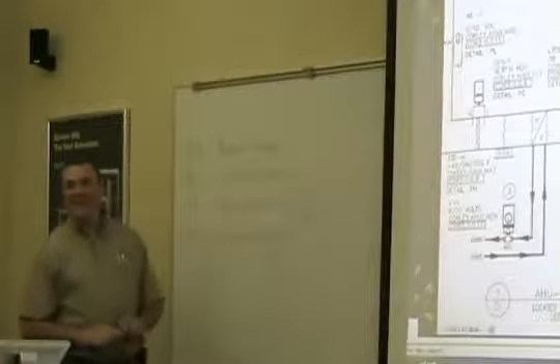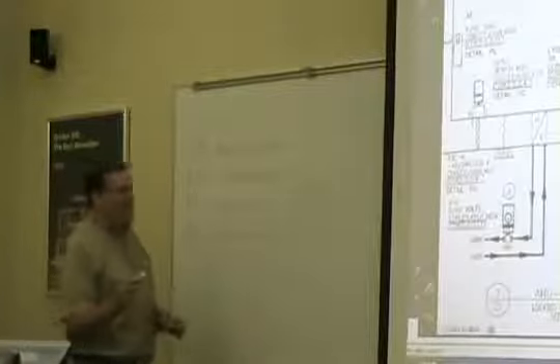Increase in temperature because of the fan. Right. Okay. You can pick up 2-3 degrees of heat across the fan. And some customers, some engineers want to just be able to see that. Actually, on ours back here, we were seeing a 10-degree rise from this point over to this point. Okay? And we thought that was crazy. So you got rid of one of the stats? Yeah, we did one of them. We got it on the screen.